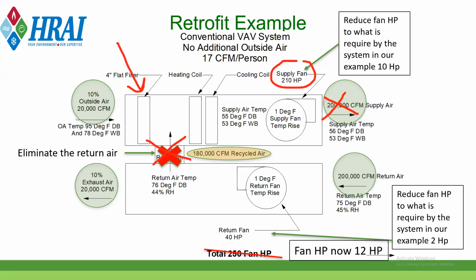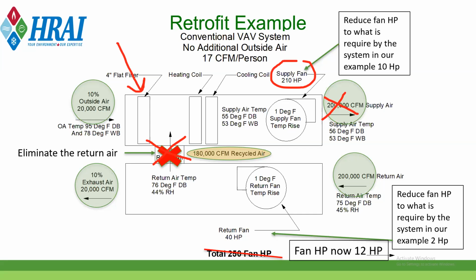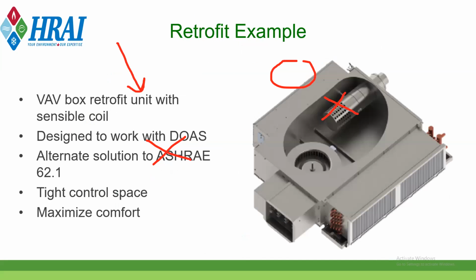That's pretty much it, where it's all coming from. The active chill beams, of course, would be down in the zone. Even if converting the building to active chill beams is not an option, and the building has already been heated and cooled with a VAV system, there are some VAV retrofit boxes available, such as is shown in this example, that provide similar performance. The fresh air ventilation would be piped to those, and then there's a hydronic coil there that you can still supply with hydronically heated or cooled water, whether it's heating or cooling mode. And there often is a little fan inside as well that you can switch on and off to add some additional fan power if needed in that local space.